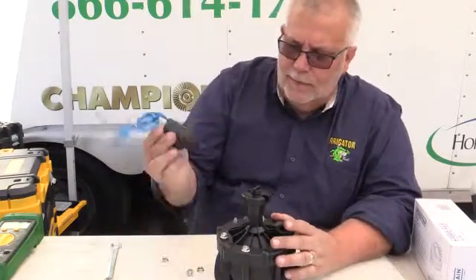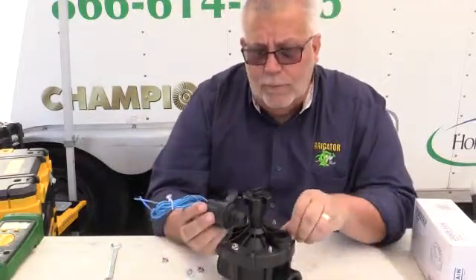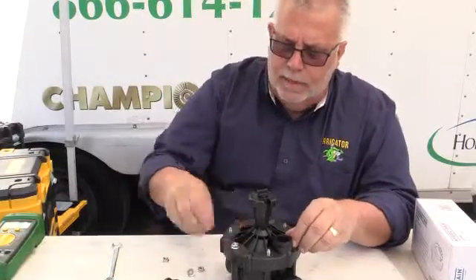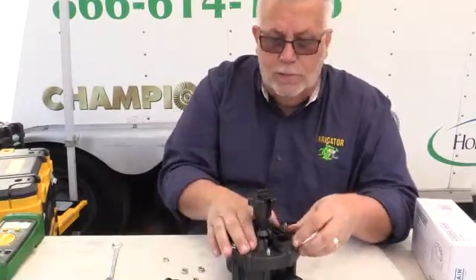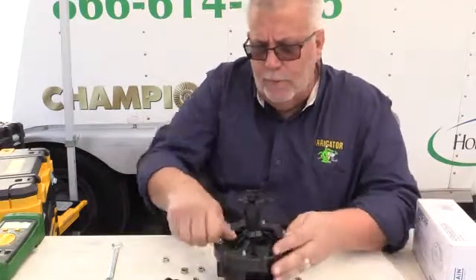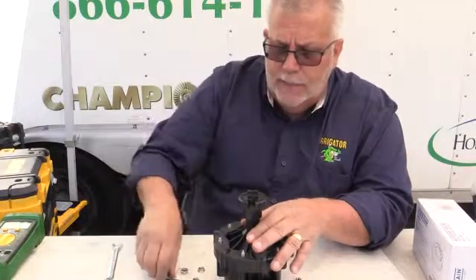I do like that it has a very nice solenoid. The ohms reading on this solenoid is about 21, which is a very nice reading that works really well on long runs of wire. The solenoid is very competitive — you can buy it and make it interchangeable with other ones.